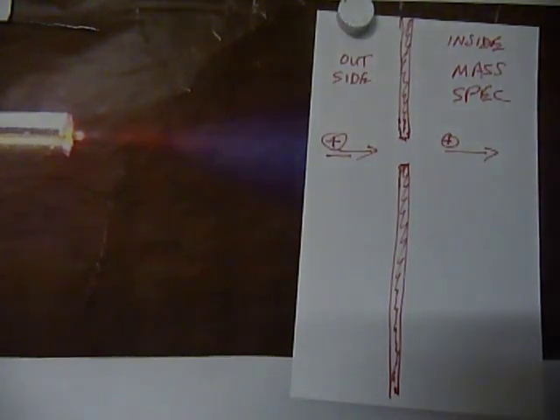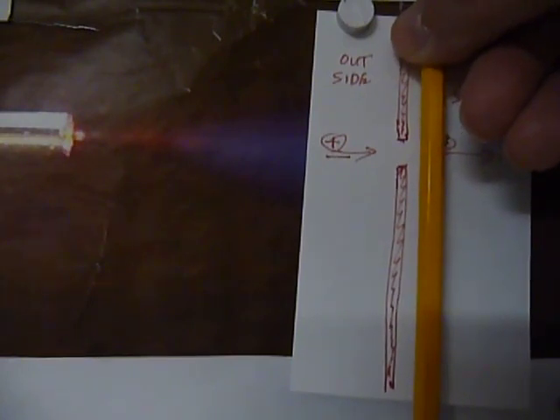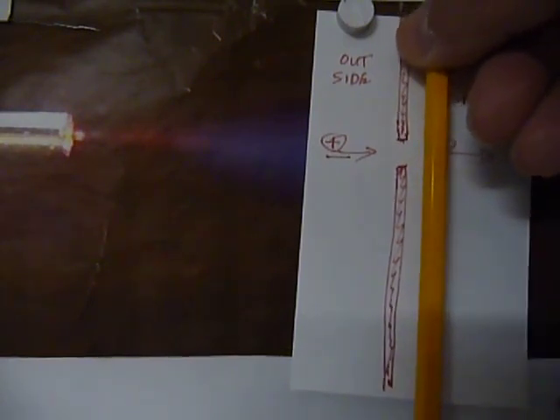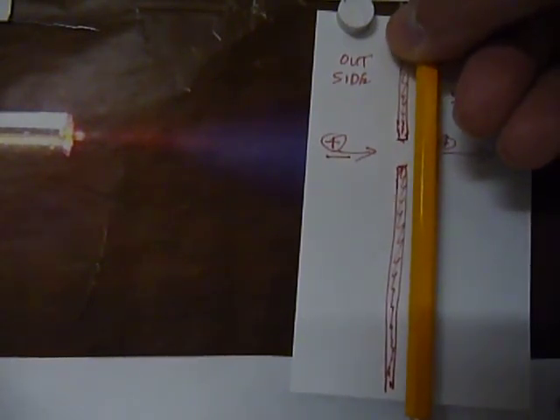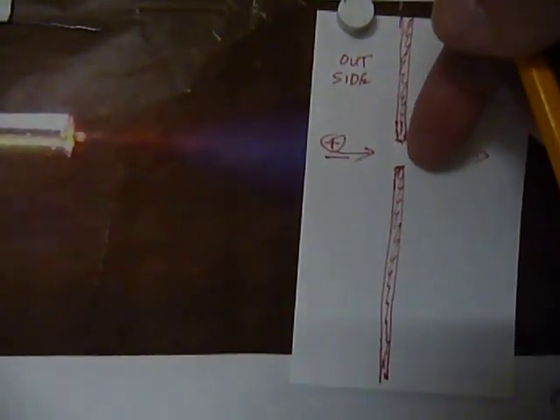The other way we could induce collision is suppose we had some sort of a gas barrier that we increase the density. And so, that's what the sweep gas setting does on the exactive.